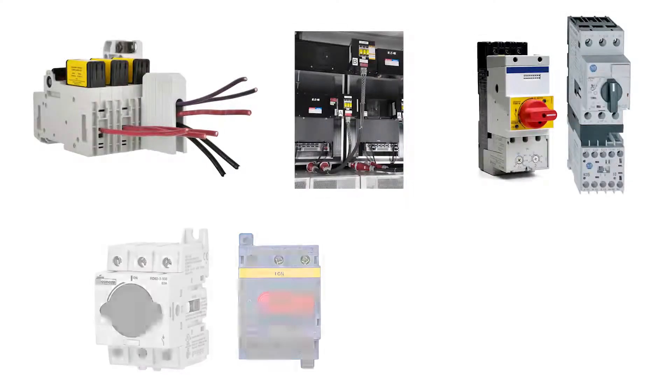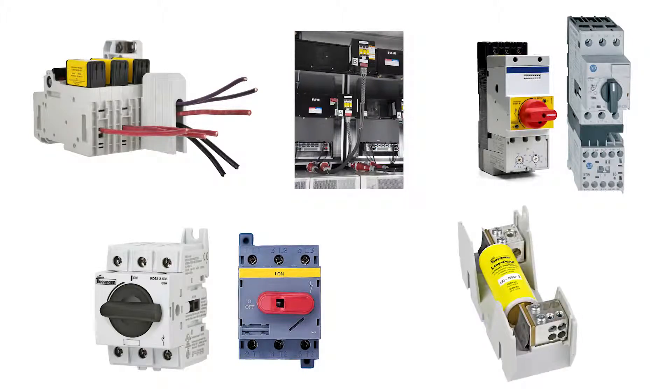Fuses can protect components and equipment from extreme thermal and magnetic forces by clearing the fault current within the first half or quarter cycle. Conductors, busway, motor starters, switches, and other devices can be well protected with current limiting fuses.